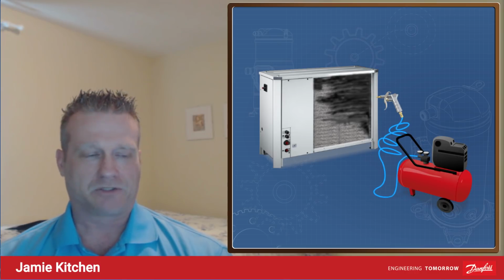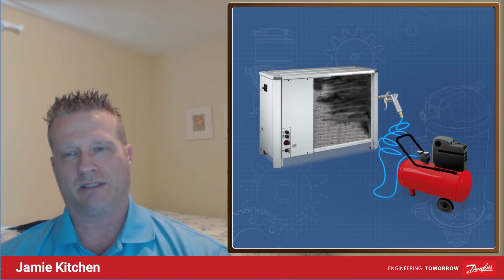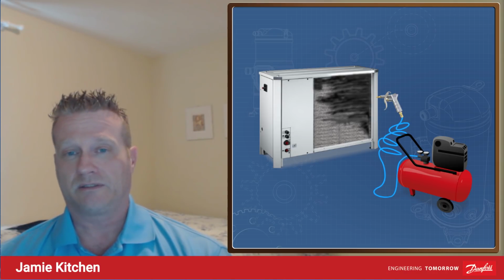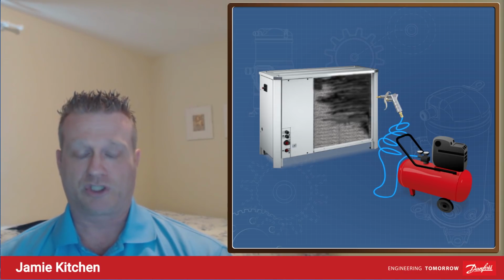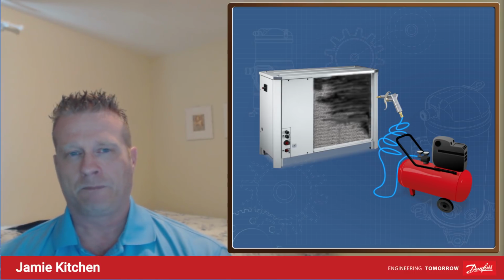Okay, so checking airflow, look at the condenser outside or inside if it's inside. Is it clean? Is it being blocked? Is there a fence around it? Is there a hedge around it? You'd be surprised the stuff we've cleaned away from outdoor units. I've got pictures of tree and bush stumps and stuff like that around an outdoor unit where there used to be a hedge or a tree growing.